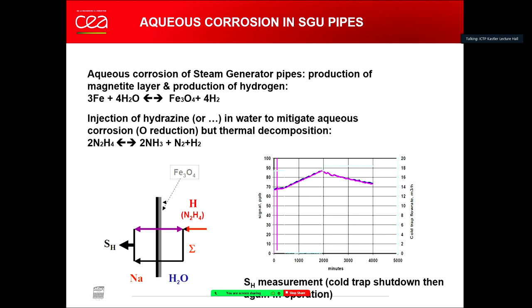the impact also on the pollution, and also maybe on the release of tritium, because the tritium, I will show you after, comes from the primary circuit and goes through the walls of the intermediate. You know that generally hydrogen, protium or tritium, has a property of going through the walls, okay? This is the only element that is able to go through the wall at a high temperature. So it's important to know this source.